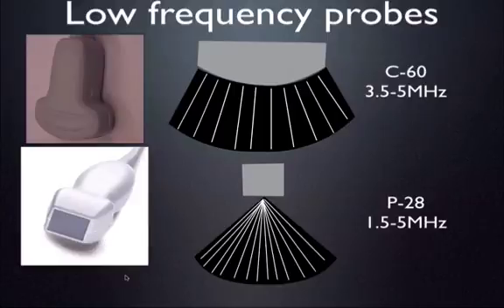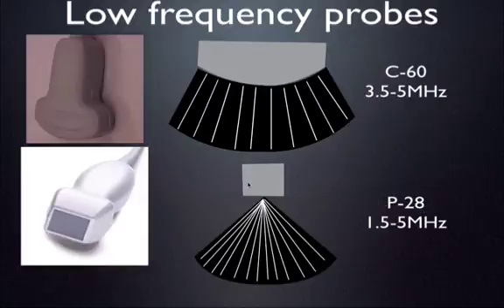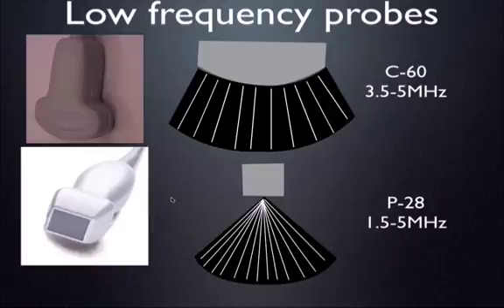The phased array probe, sometimes called the cardiac probe, is also a low frequency probe at 1.5 to 5 megahertz. It is 28 millimeters across the scan face. Its major strength is its small footprint, which allows you to look between the ribs at the heart, lung, or whatever you're trying to examine in the thorax. You can use it for the abdomen, but it's most commonly used for thoracic imaging.